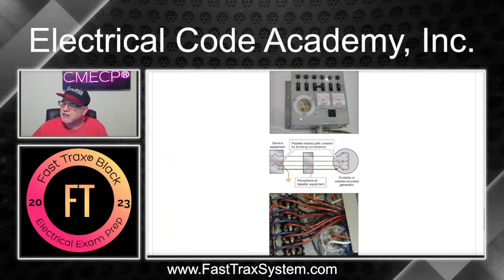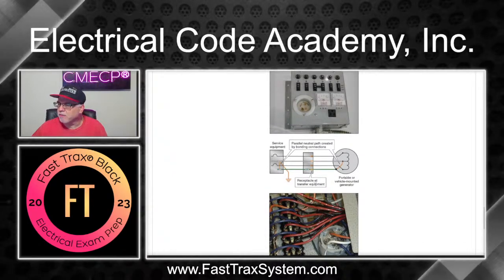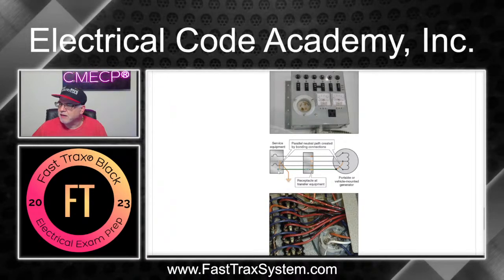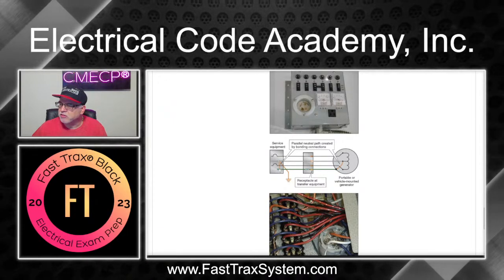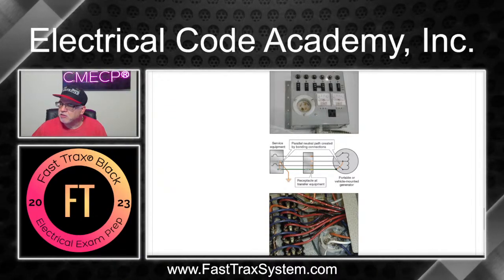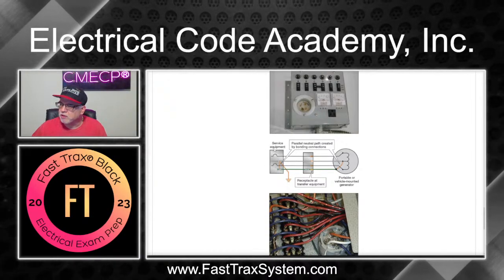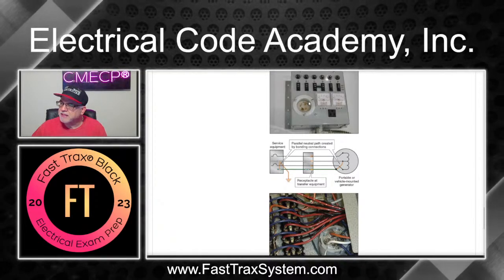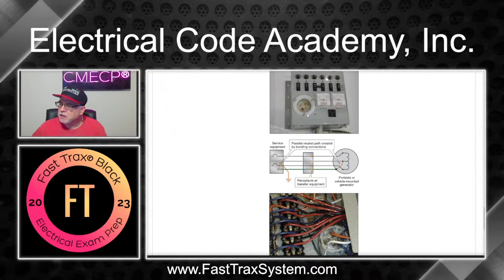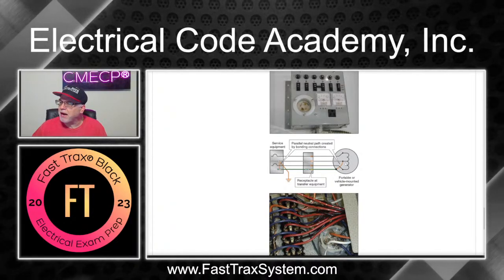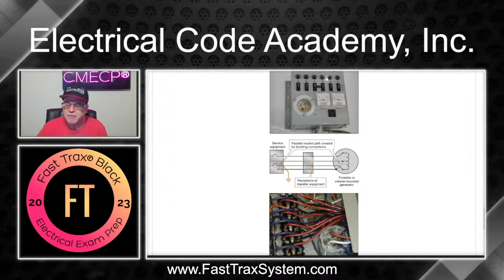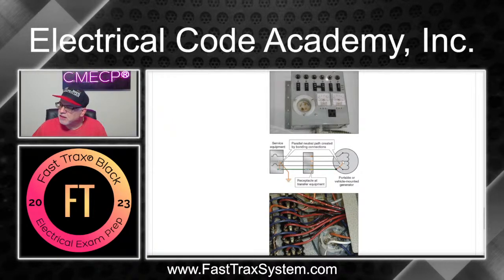All right, so in looking at this transfer switch, and you can look in right here, here's your service equipment, okay? And right here, you've got your service equipment, you've got your main bonding jumper, everything's installed, and here's your electrode. So this is your service. And here's the receptacle right here. This piece right here is the actual depicting this receptacle, right? So here's what happens. Now, if you go buy a portable generator, okay, and in this case, this is one that is bonded, right? So this is bonded right here.